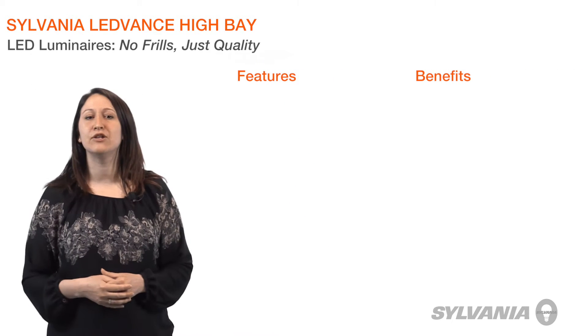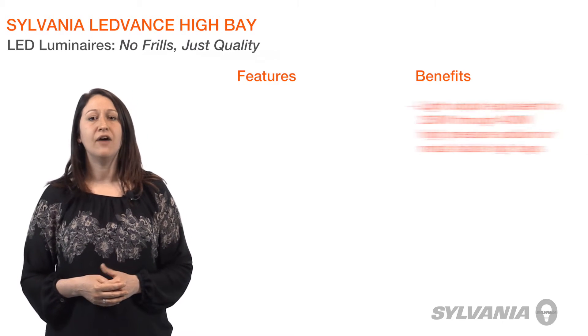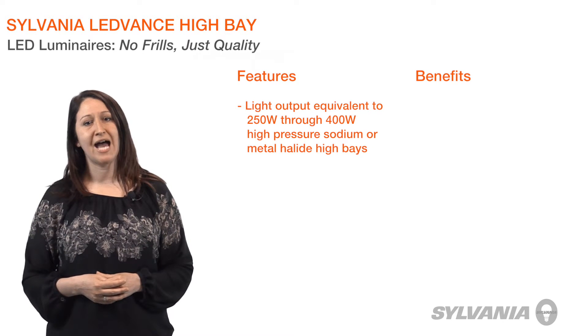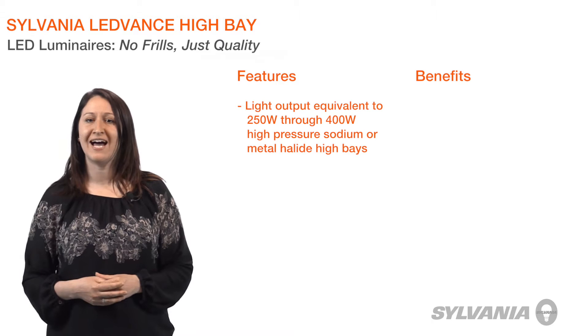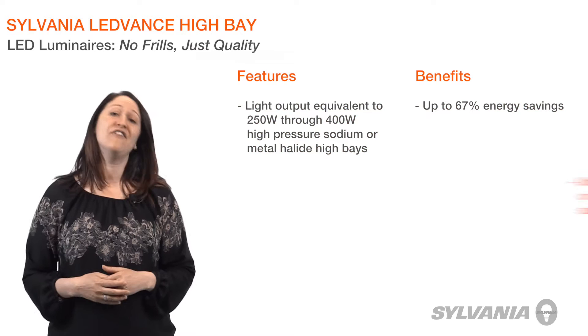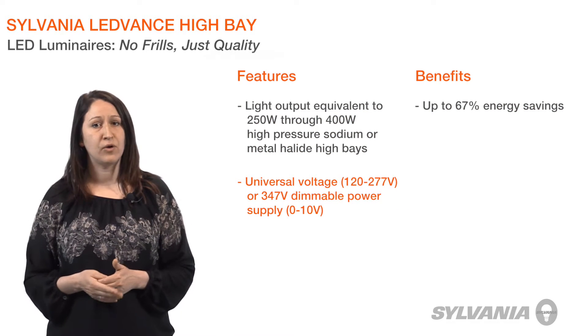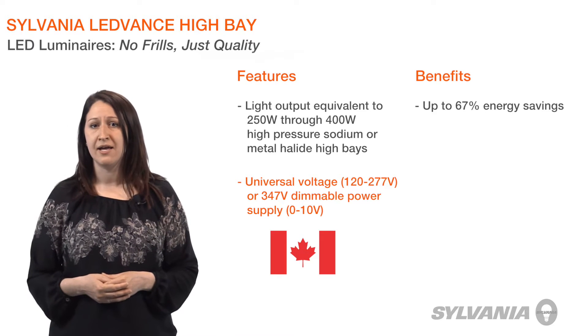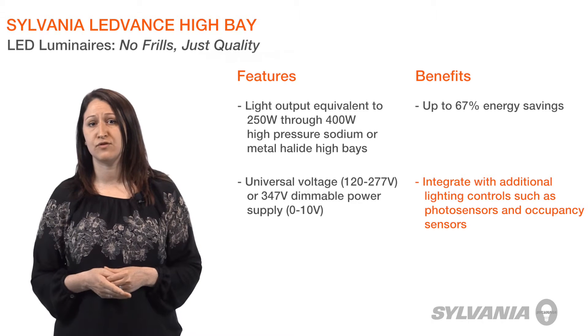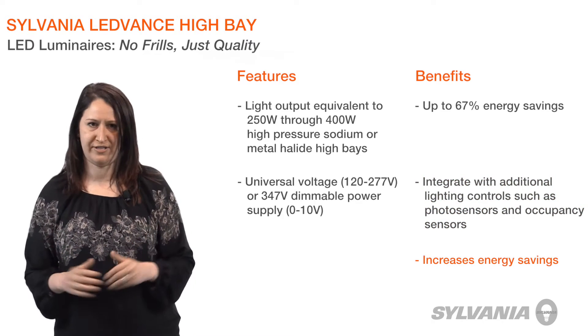LEDVANCE High Bay Luminaires are extremely efficient. They are ideal in new installations or as replacements, offering light output equivalent to 250 watt through 400 watt high pressure sodium or metal halide high bays, while delivering energy savings of up to 67%. They are available with a universal input voltage 120 to 277 volt, or a 347 volt dimmable power supply that is also compatible with 0 to 10 volt controls such as photosensors for daylight harvesting and occupancy sensors, resulting in even greater energy savings.